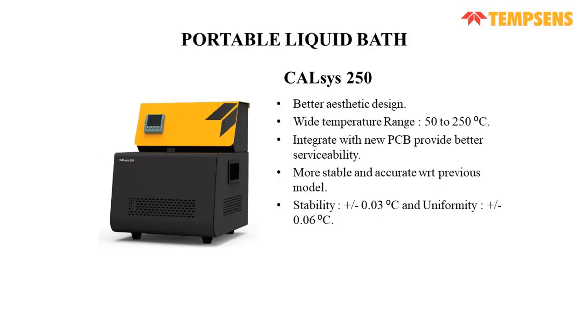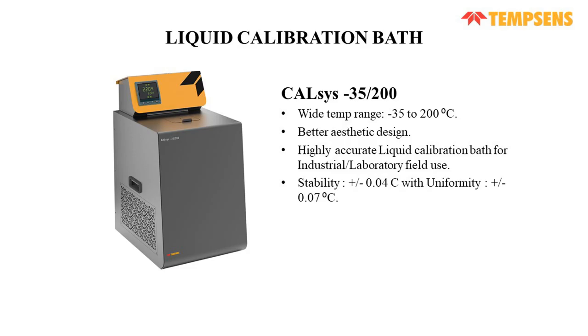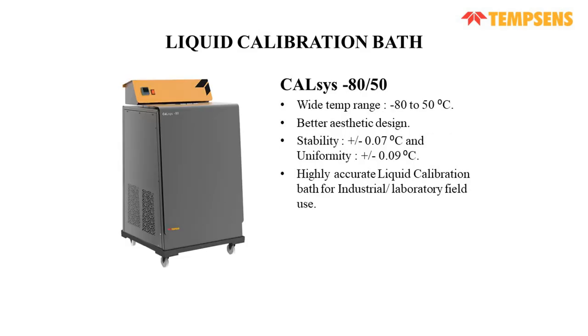Then we have the CALsys 250. It is a liquid bath model, and the temperature range for this one is 50 to 250, with stability of plus minus 0.03 and uniformity of plus minus 0.06. Then we have the Calcis minus 35 to 200, with a temperature range from minus 35 to 200, stability of plus minus 0.04 and uniformity of plus minus 0.07. Then we have the Calcis minus 80 to 50. The temperature range is minus 80 to 50, with stability of plus minus 0.07 and plus minus 0.09 uniformity.